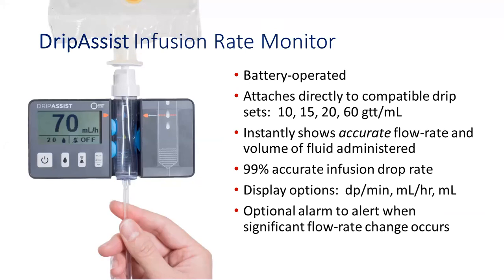So the device itself is about the size of a cell phone or a deck of cards. It runs off of one AA battery, and it was designed to work with any drip set. So there's 4 sizes of drip sets around the world. Some countries only use 1 or 2 sizes, but we wanted this device to work with any size that a facility would have. So when you first turn on the device, you have the opportunity to tell it what kind of drip set you're using, what size, whether it's a 10, 15, 20, or 60.